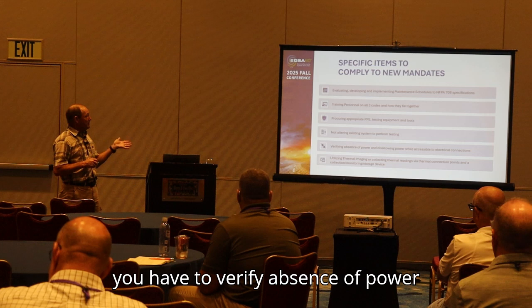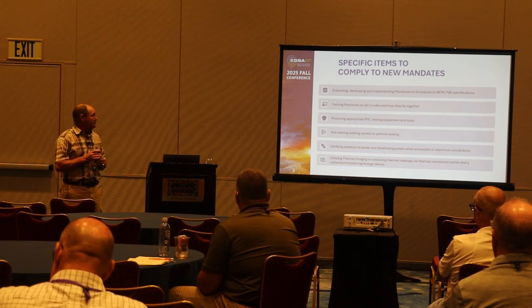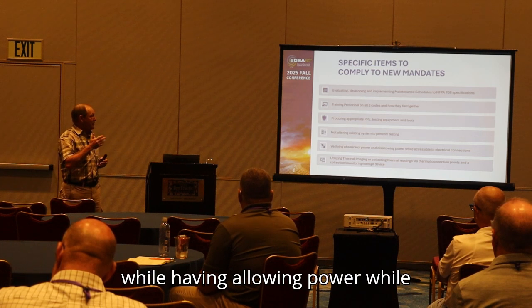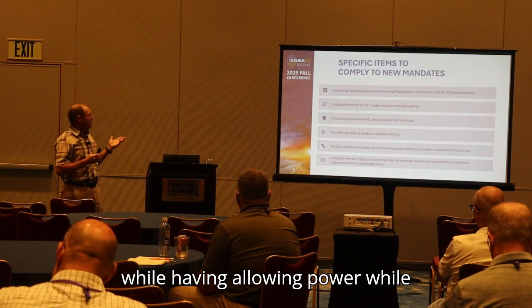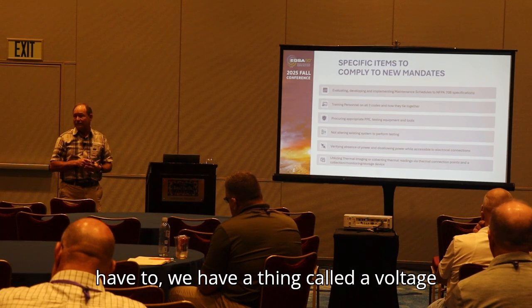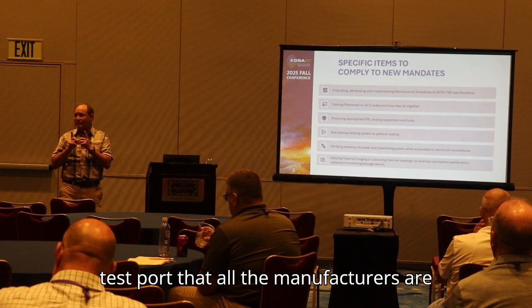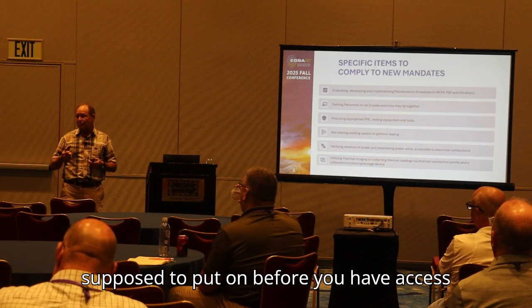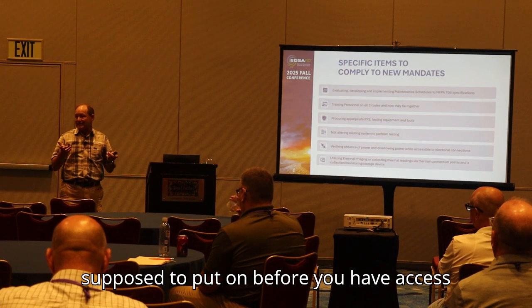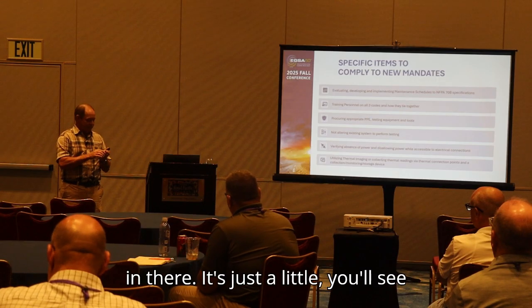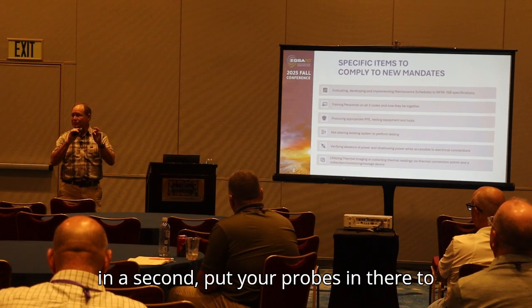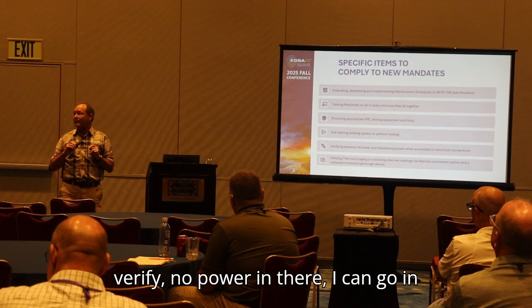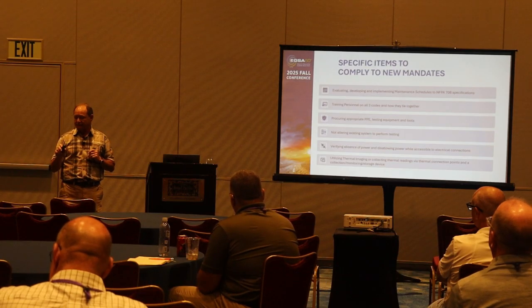But you have to verify absence of power while disallowing power while accessible to electrical connections. We have a thing called a voltage test port that all the manufacturers are supposed to put on before you have access in there. It's just a little, you'll see it in a second. Put your probes in there to verify no power in there, then I can go in there.